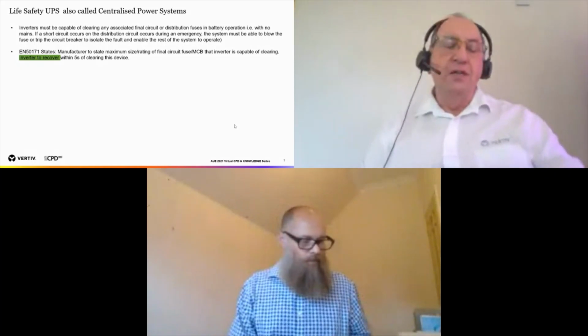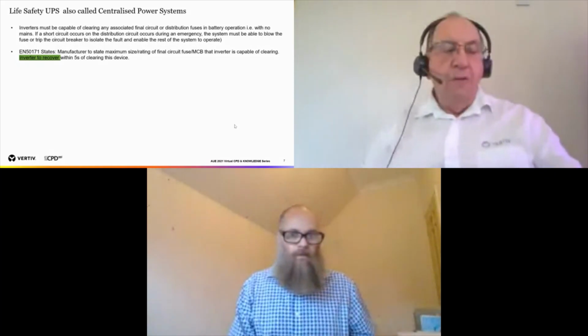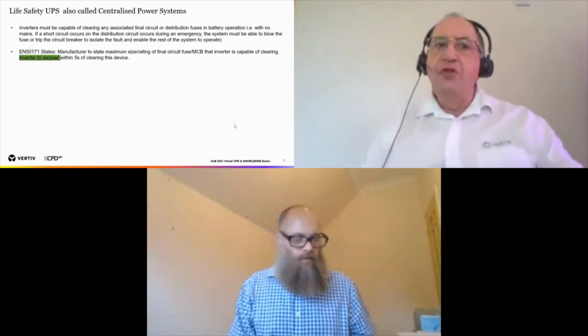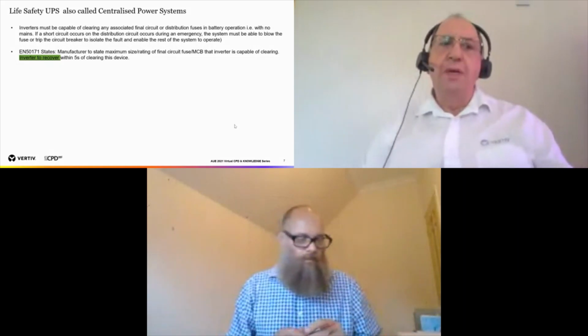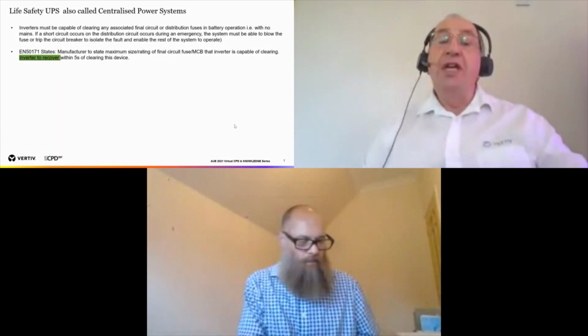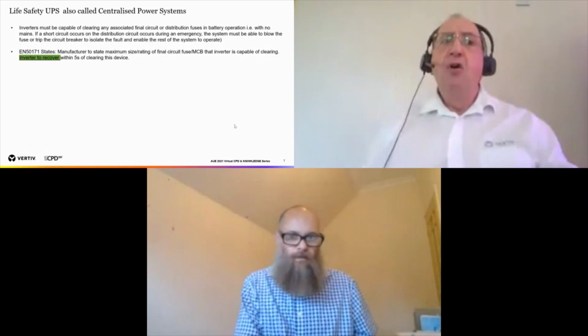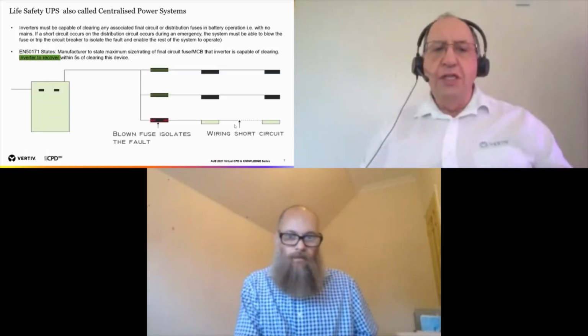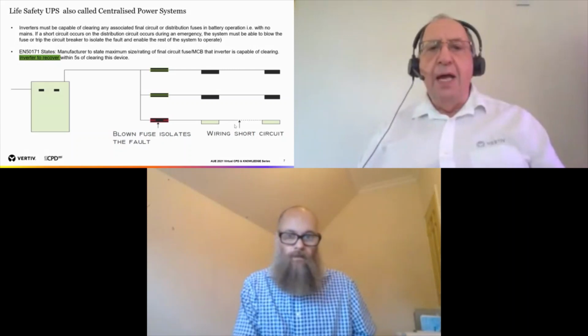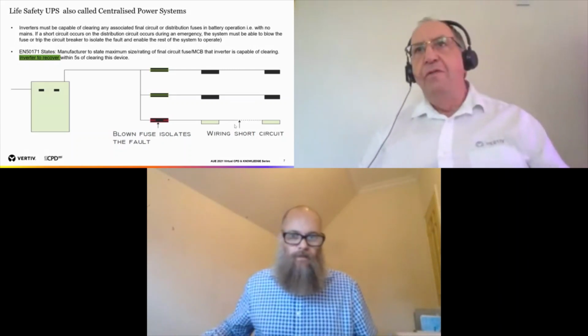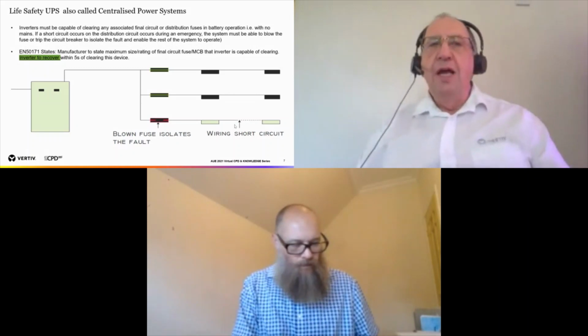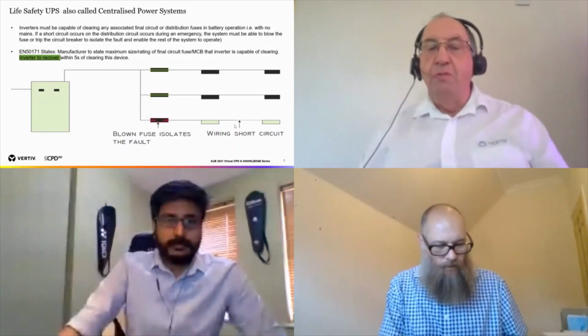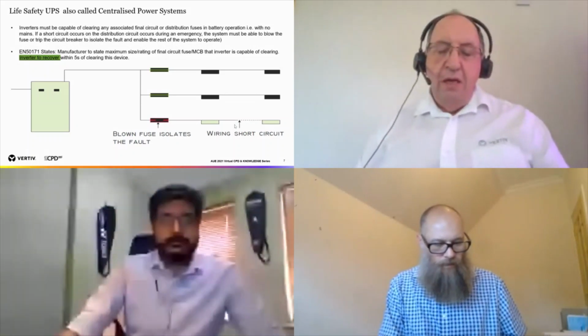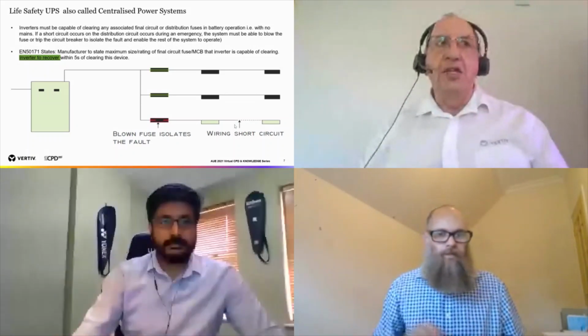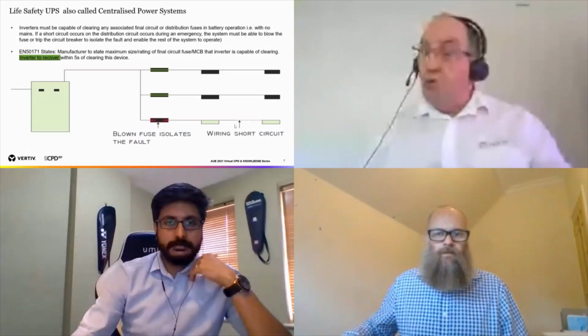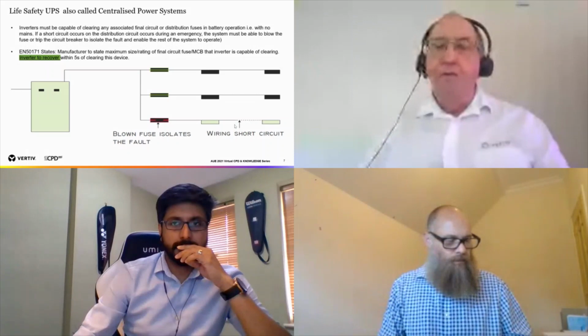So the idea is that there's a mains failure, there's a fire in the building, part of the electrical infrastructure gets a short circuit, the system should be able to clear that short circuit and then recover and put the circuit back on again, all on battery operation. So it's quite a specialized device. I just ask people that if you are specifying a UPS and it is a life safety, or it could be graded as a life safety system, maybe by a court, then really think about 50171 systems.